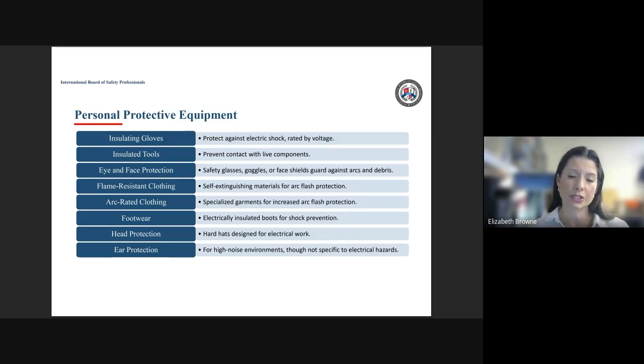Also, head protection. We have hard hats that are designated as E, or designated for specifically electrical work. They do have impact protection, but they also will protect the head from up to 20,000 volts. And then for high noise environments, we always want to have hearing protection. But if an employee is working somewhere where there's a potential for an arc blast, we want them to have hearing protection as well, because those can be very loud.